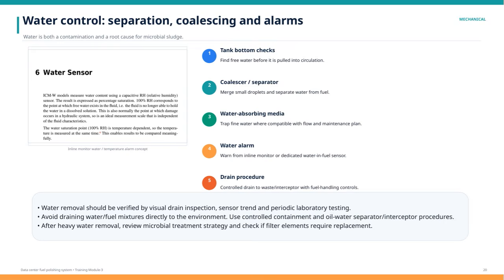It's important to verify water removal through visual drain inspections, monitoring sensor trends, and periodic lab tests. Avoid draining water-fuel mixtures directly into the environment by using proper containment and oil-water separation procedures. After significant water removal, review microbial treatment strategies and check if filter elements need replacement to maintain system health. All these steps help ensure reliable fuel quality and protect the entire system from water-related issues.